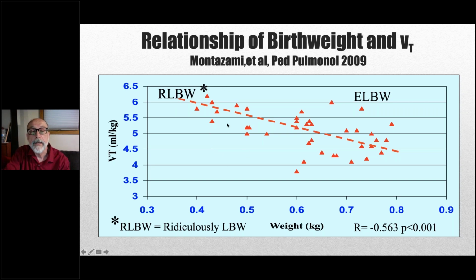And this is a function of the dead space of the flow sensor. The baby weighs 800 grams. The dead space is 0.8 to 1 ml, depending on which flow sensor you use, and that stays the same. If the baby's lungs are half the size and the flow sensor is the same size, you need some compensation. So a little bit bigger tidal volume for that reason.